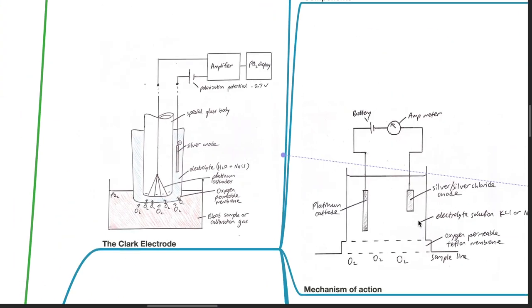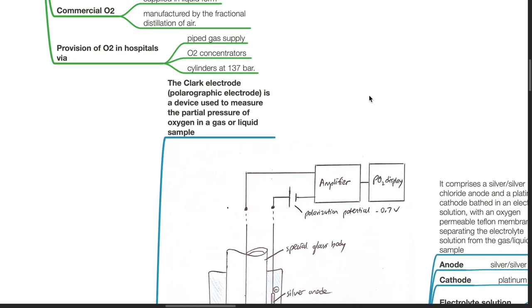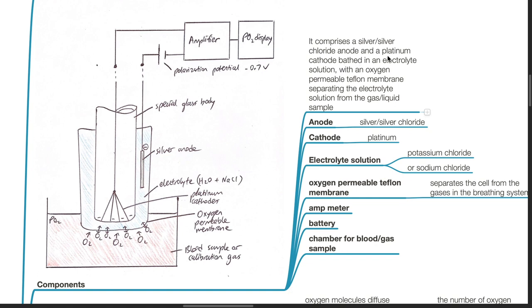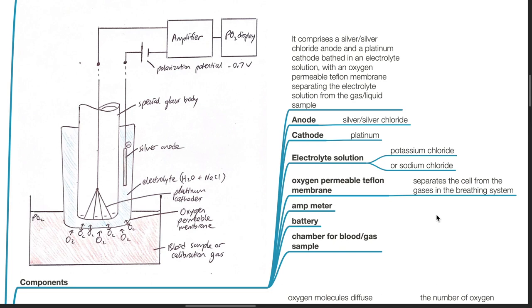The Clark electrode, or polarographic electrode, is a device used to measure the partial pressure of oxygen in a gas or liquid sample. Components comprise a silver-silver chloride anode and a platinum cathode bathed in an electrolyte solution, with an oxygen-permeable Teflon membrane separating the electrolyte solution from the gas or liquid sample. The anode is made of silver or silver chloride, the cathode of platinum, and the electrolyte solution is potassium chloride or sodium chloride. There is also an ammeter, battery, and a chamber for blood or gas sample.